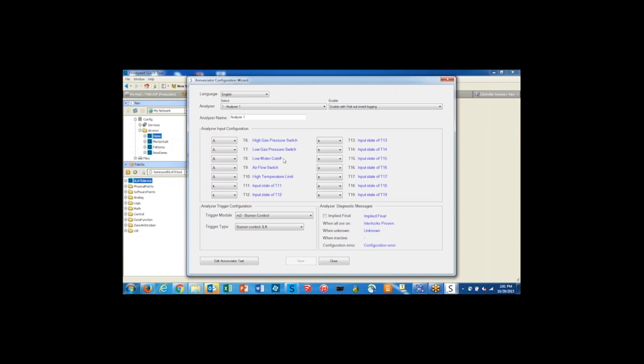I have five different interlocks: high gas, low gas, low water cutoff, air flow switch, and high temperature limit. These are the five interlocks that are on my interlock string that I want to be able to troubleshoot in the event that I lose one of my interlocks.